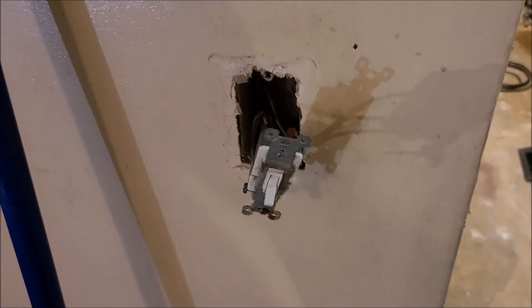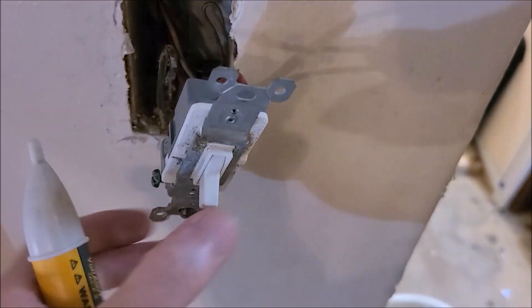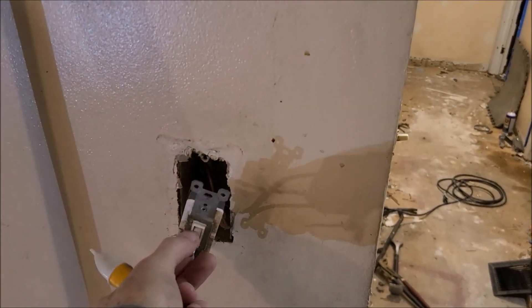I'm assuming - let me show you something. I'm going to assume something here. Can you see the lights are off now? No power. Now we got power - the black wire's got hot going up into the attic. So my assumption is someone's tapped into this wire for some reason to feed this receptacle here, or not a receptacle but the light switch or this light. The switch works, it's doing its job, but it should not be tied in with this three-way at all - it's really bizarre.